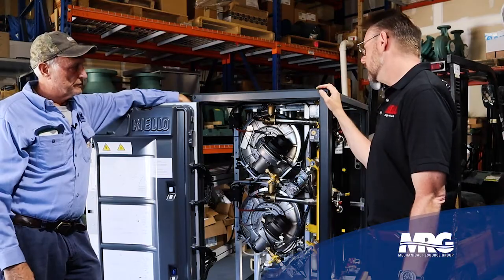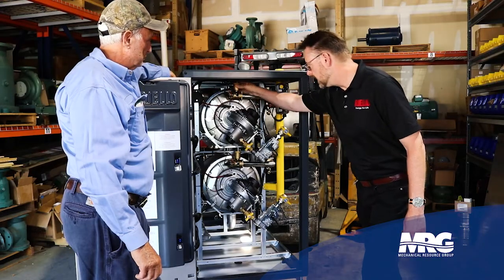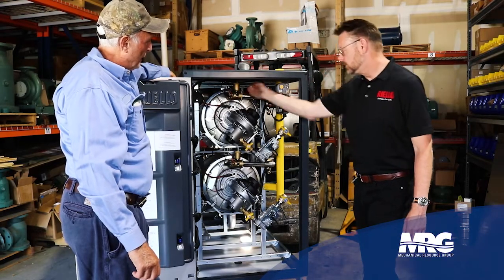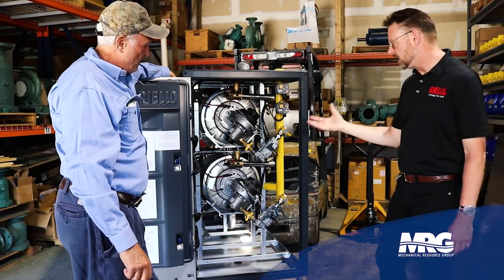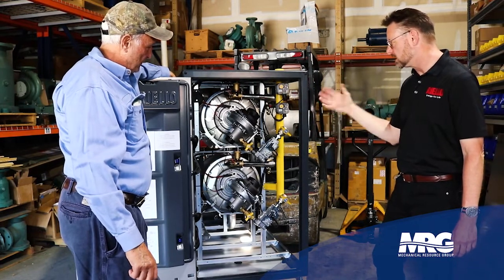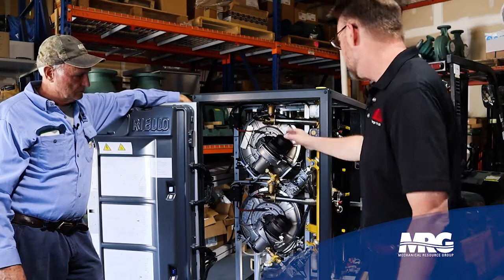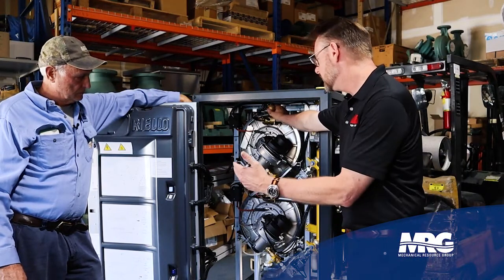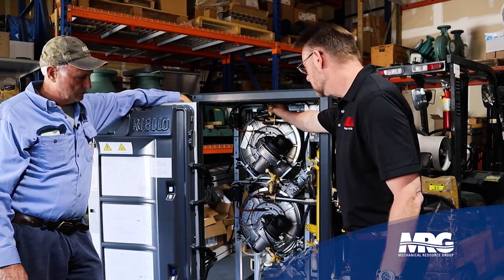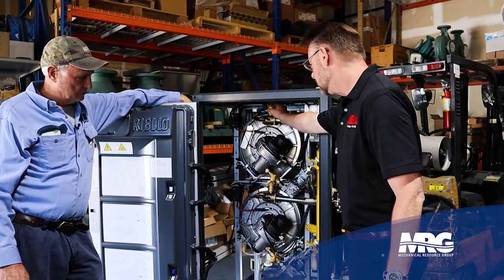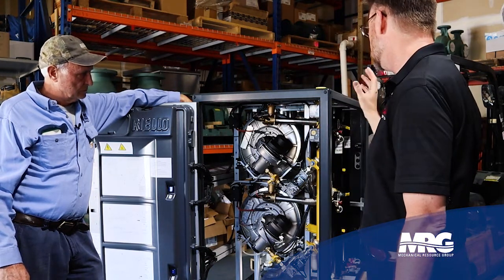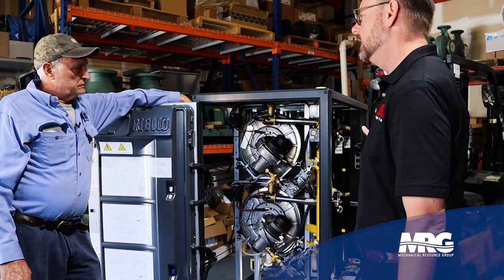Away you go. Okay, they're a little different in that at each point where you're going to have the most air made available, free from the water because of inverse solubility, et cetera, we're not going to get into physics, we have these air vents. So we have an opportunity to fend off that issue that would require a failure at the helix level to resolve. So circulator, you were down, you had to get a circulator.